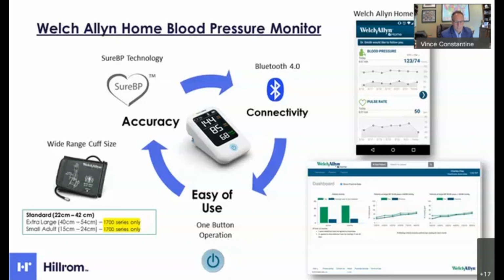There are really two pieces that form the accuracy of a device like this. First of all, it's cuff sizing. The device comes with a standard cuff, which is 22 centimeters to 42 centimeters, or about 8.5 to 16.5 inches. We also have the capability of an extra large cuff, 40 to 54 centimeters, which is approximately 15.5 to 22 inches. And if you needed it, we also have a small adult cuff.